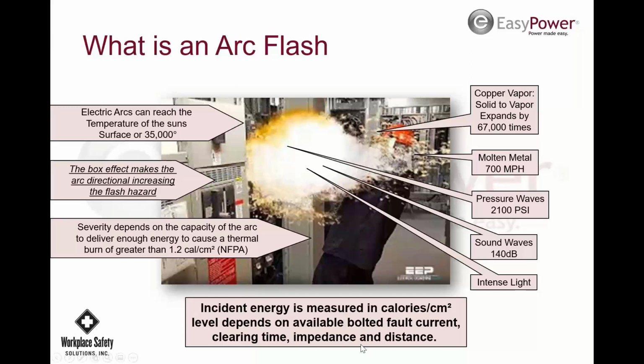The impedance. So impedance is like the electrical version of resistance. It's based on inductance and capacitance, and I don't want to get too much into this because some people are more safety related than they are electrical. But if you have inductance or capacitance, that will have an impact or impede the current from flowing through that conductor, just like resistance. And so the higher the impedance, it's going to drop the fault current, but it's going to increase the clearing time. So you could have a 300-foot run of wire and have a certain calorie rating at this breaker, and 300 feet away feeding a disconnect, it's actually going to be higher because the clearing time is going to change. The fault current's going down, but the clearing time is going up. So it's going to allow this arc flash to go out a little further.